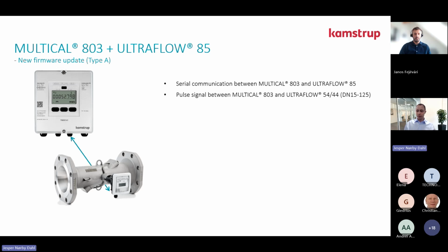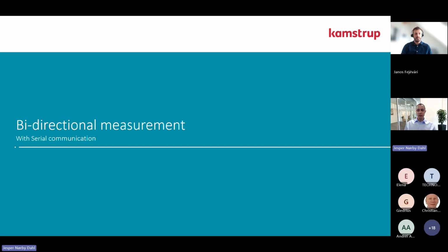Then we come into a big new thing also, which is possible because of the serial communication, and that's very important to say. Bidirectional measurement, meaning now with ULTRAFLOW 85, we have the possibility to measure the flow, both going forward, but also reverse flow. But this requires serial communication. So you will have to have the right PCB version of the Multical 603, so the S or the U version, or the updated Multical 803 firmware. But then we will have the possibility to do bidirectional measurement, measuring the flow and also the energy consumption in both directions. And what is very important to mention, it is also MID approved in both directions. So not only in one, but in both directions it is MID approved.